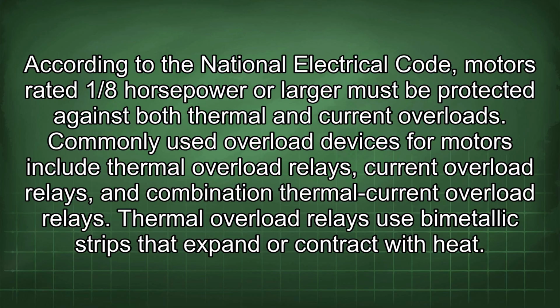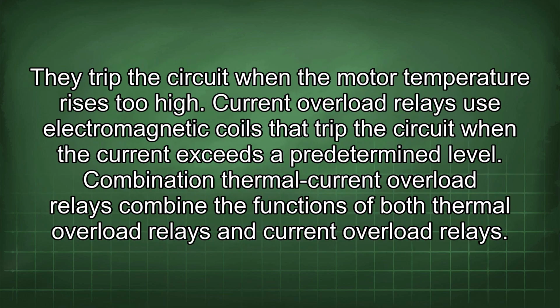Thermal overload relays use bimetallic strips that expand or contract with heat. They trip the circuit when the motor temperature rises too high. Current overload relays use electromagnetic coils that trip the circuit when the current exceeds a predetermined level. Combination thermal current overload relays combine the functions of both thermal overload relays and current overload relays.